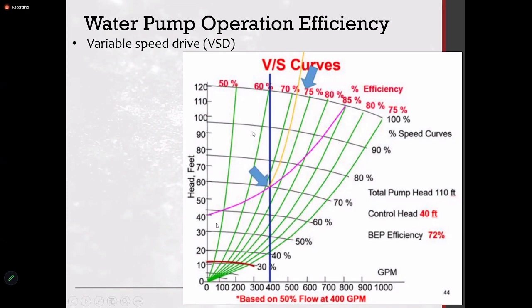So you get speed curves. Pump curves, when you install a VSD, you get speed curves. So this is your 100% speed, 90, 80, 70, and so on, it comes down. And if this is your system curve, and if this is the BEP, you run at an efficiency of 70%, maybe at a speed of 70%. So the advantage is you will not go wrong. Even if you go to 60, you can always come back to 70 and say, okay, this is the exact point we want to operate. So that's the advantage of VSD.